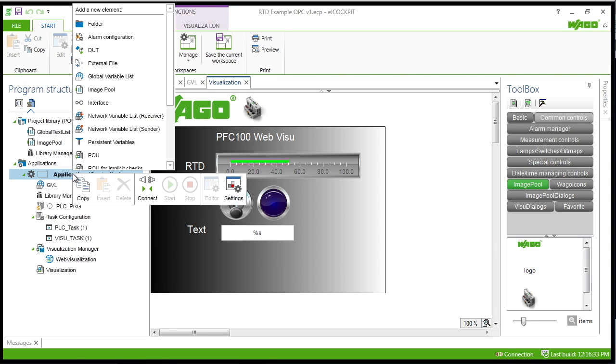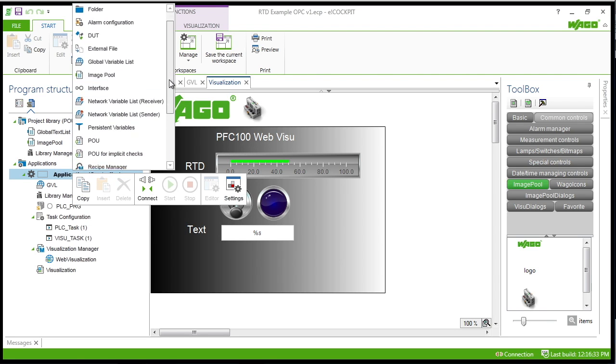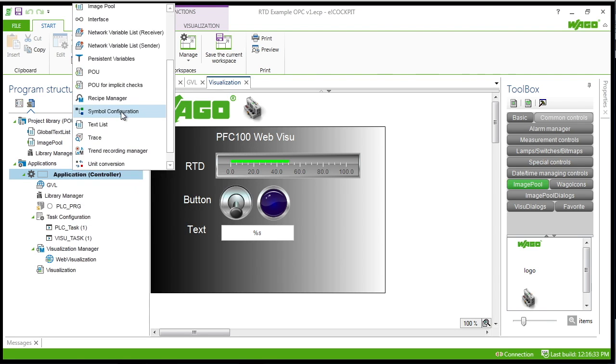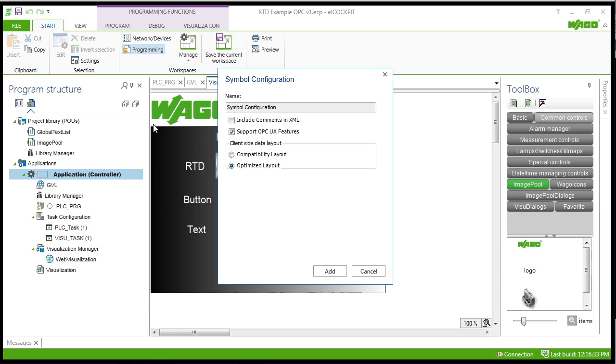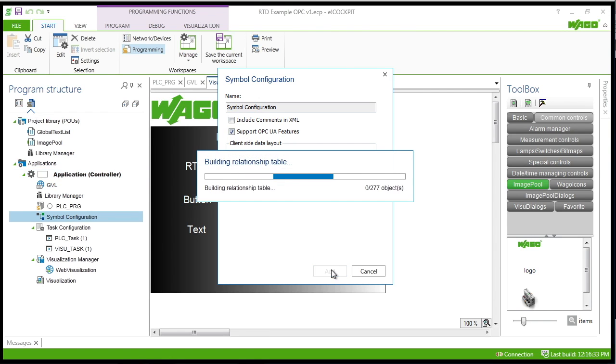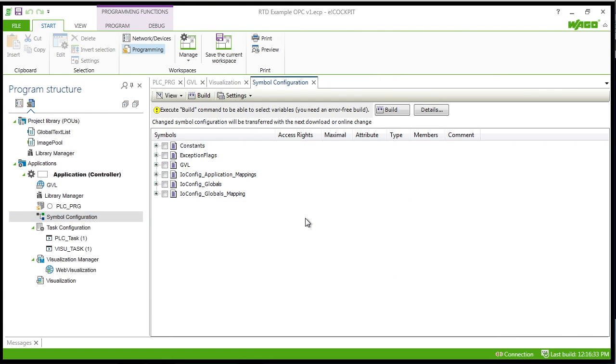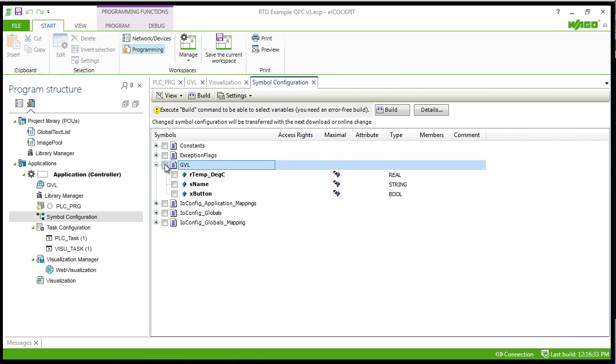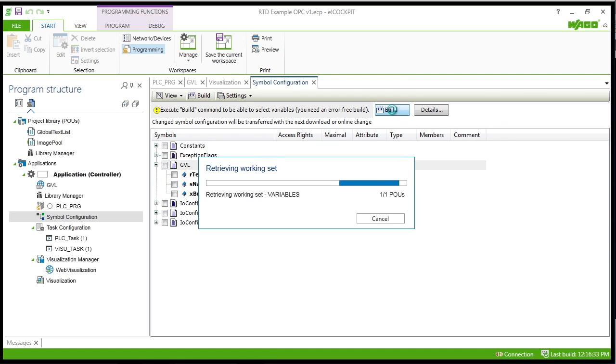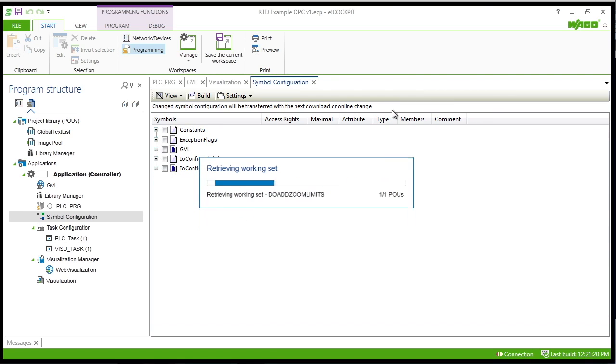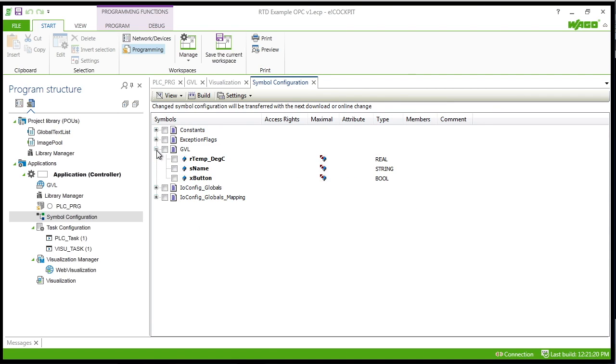So if you right click on application and click symbol configuration and check the support OPC UA features, that'll bring up this context where you can click build and then you just select the global variables and that will create the OPC objects for you.